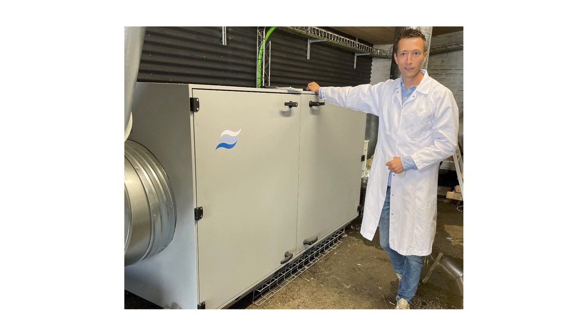Well, the outside moisture quantity is calculated using the known humidity and temperature of outdoor air, and the rate of air exchange within the area in question, the physical size of the area, and lastly what humidity and temperature ultimately needs to be. And once all these details are determined, a psychrometric calculation can be done. Now, this precisely determines the volume of moisture the dehumidifier will need to remove from the incoming outside air to meet the required indoor condition. Now, this calculation is something that a dehumidifier manufacturer will be able to provide guidance on.